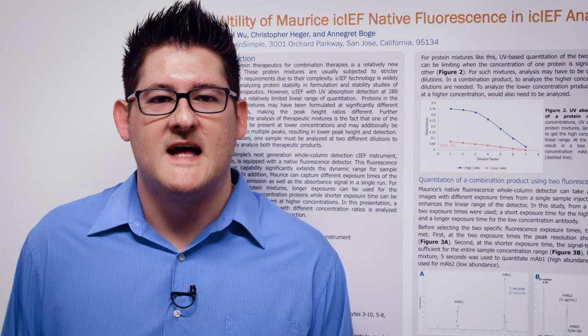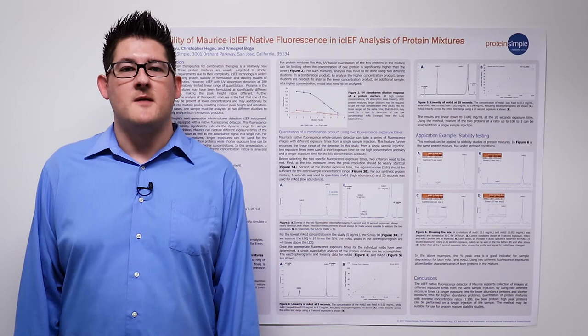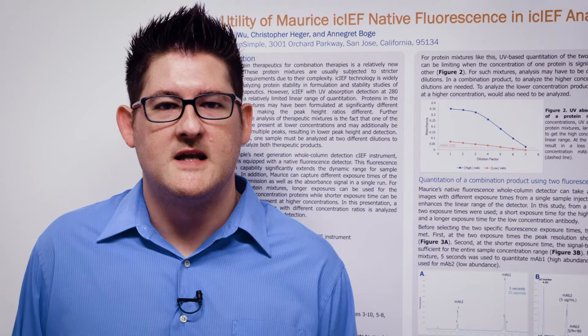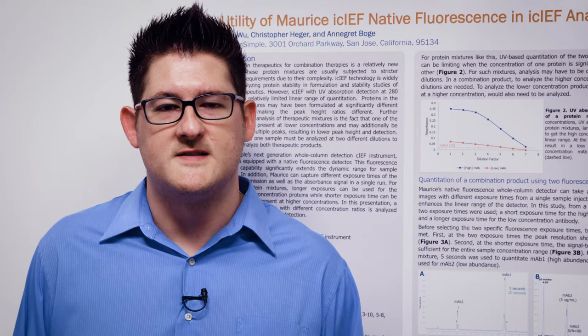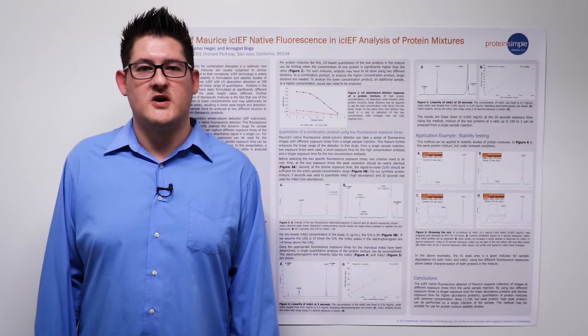Maurice adds native fluorescence to the platform, increasing the dynamic range and sensitivity of the instrument. An advantage of the fluorescence capability of Maurice is the ability to take different exposures at the same time as capturing an absorbance signal. For a therapeutic co-mixture where two products may be present at significantly different concentrations, two different image exposures for fluorescence can be used to tease apart the same sample in a single analysis.